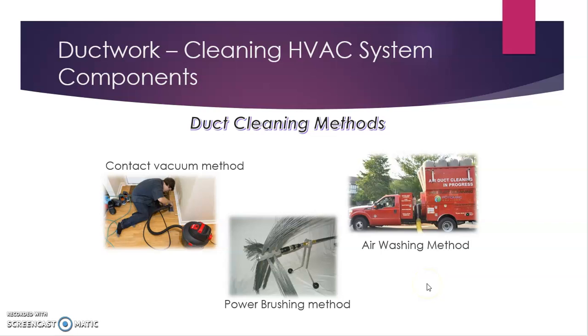So for the HVAC system component, there are several cleaning methods. For example, the contact vacuum method, same like our household vacuum. We have to do the vacuum and make sure the debris or particles are sucked in very well. The next one is the power brushing method, which is usually applied for the ducting system, and we also have the air washing method, which is also applied to our ductwork system.